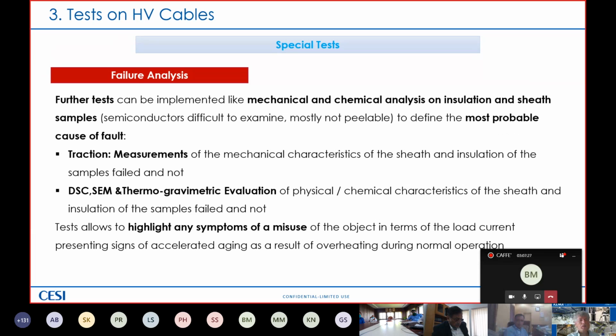Apart from the visual inspection, further tests can be implemented. For example, mechanical and chemical analysis on the insulation and on the sheath. Basically on these two main components, because semiconductors are difficult to examine, some of them or most of them are not peelable. And this further mechanical and chemical analysis will help us to define the most probable cause of fault. For example, traction, this measurement of the mechanical characteristic, is done on the cable sample and insulation on the sample failed and not failed.